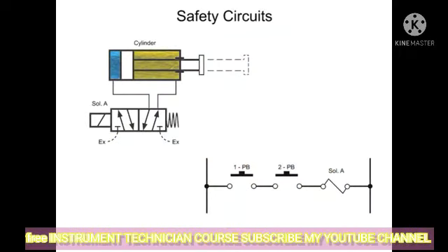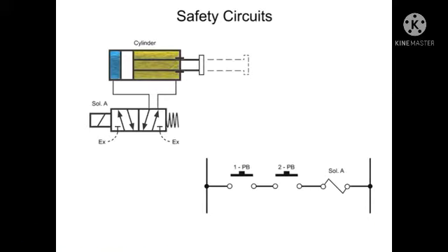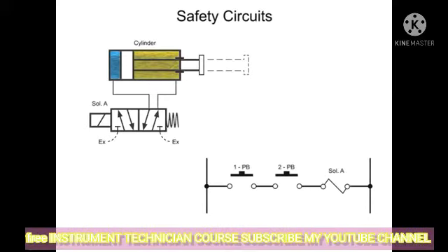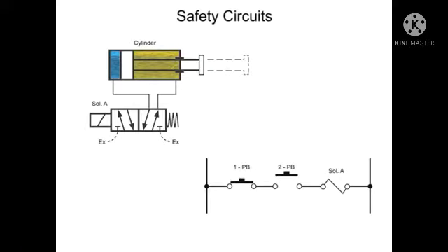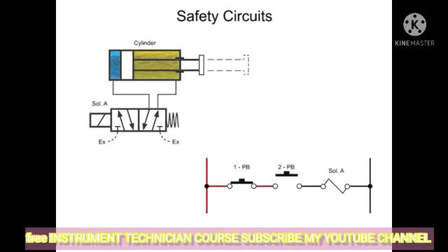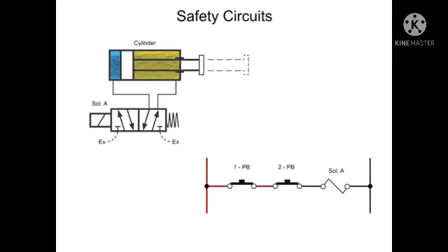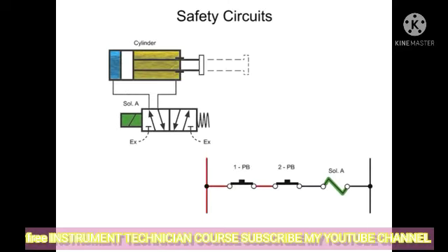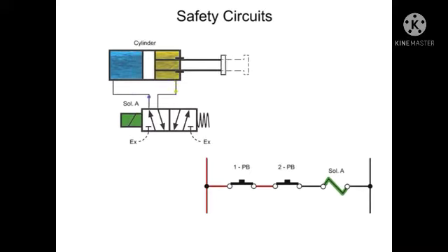This type of two-hand control is simple to install and is fairly safe if two operators are present with physically separate control panels. If only one button is depressed, the electrical connection is not made and the machine will not start. As shown in the circuit, only the actuation of both push buttons allows the solenoid to energize. The solenoid then shifts the valve to allow air into the cylinder, which produces the machine's stamping motion.